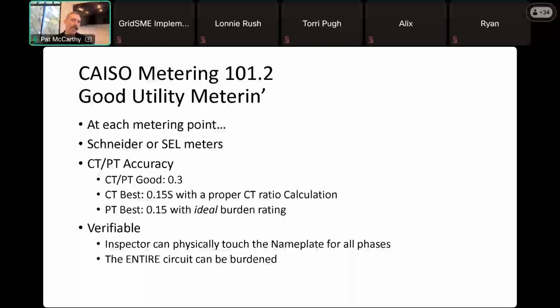Potential transformers kind of have the same thing - they've gotten twice as accurate. There's no calculation because there's not much range, but there is a way to get the ideal burden for a PT. All that means is don't go for the highest burden rating, because nothing has any burden anymore, so you're probably at the worst accuracy within the spec of that PT. The punchline here is that your current transformers, your voltage transformers, and your meter all have error tolerance, and very few things read high.